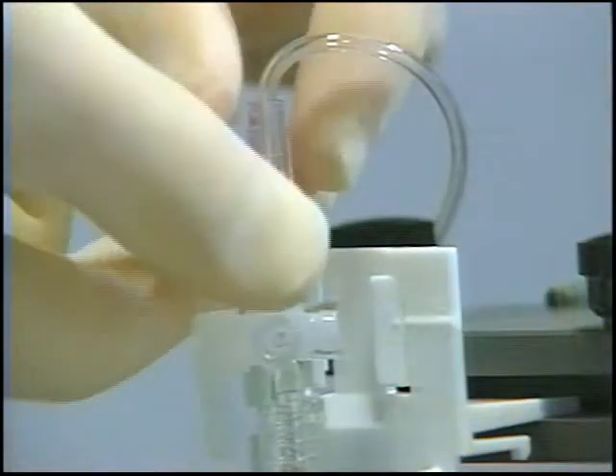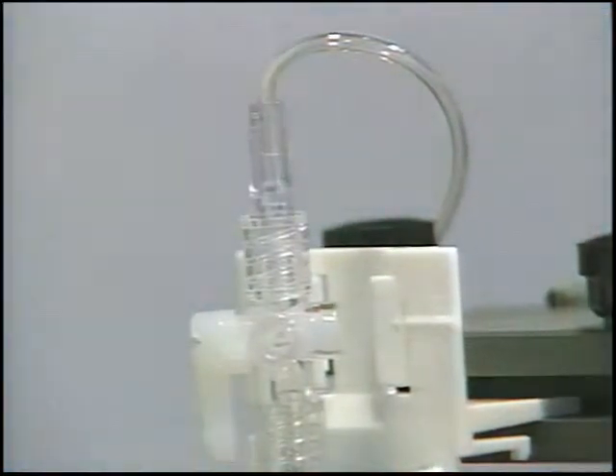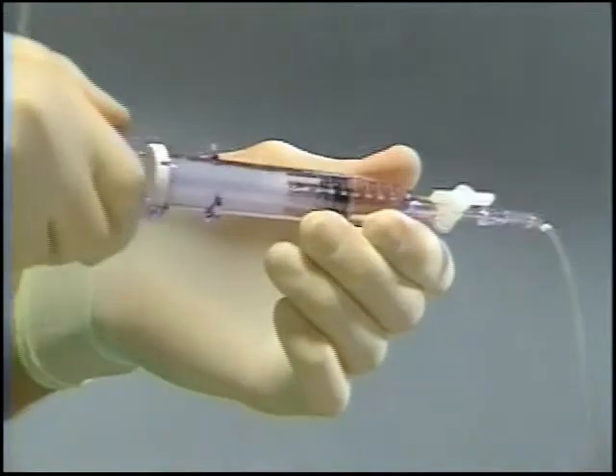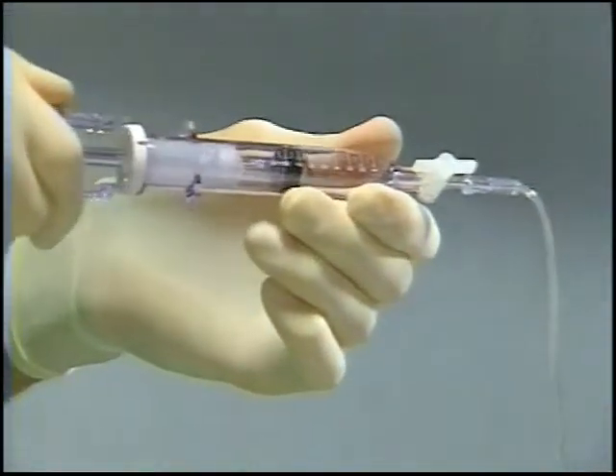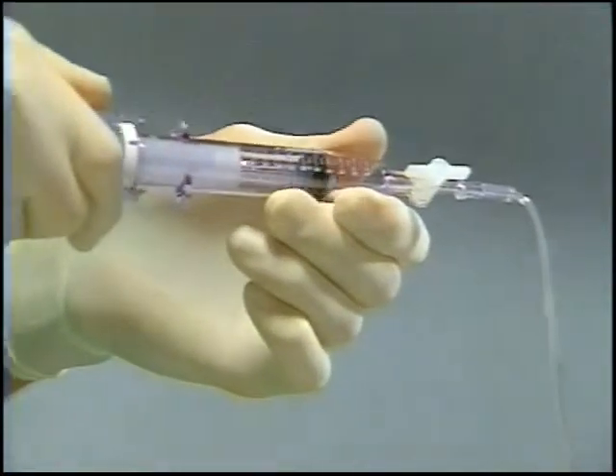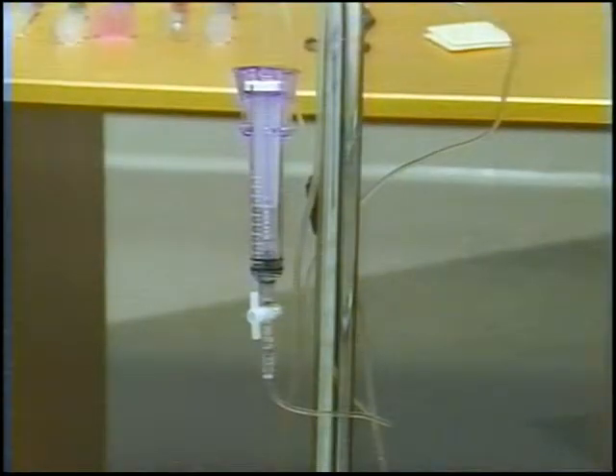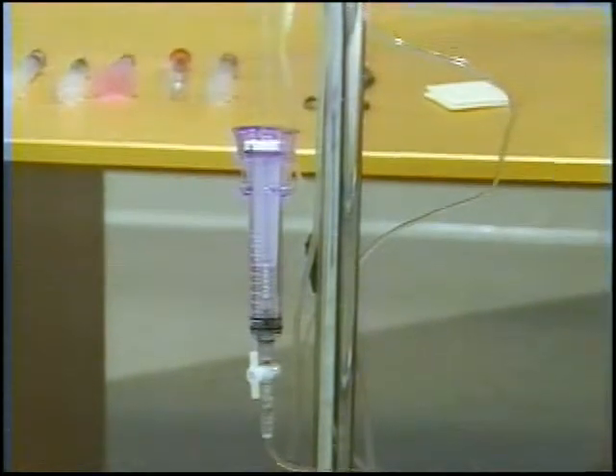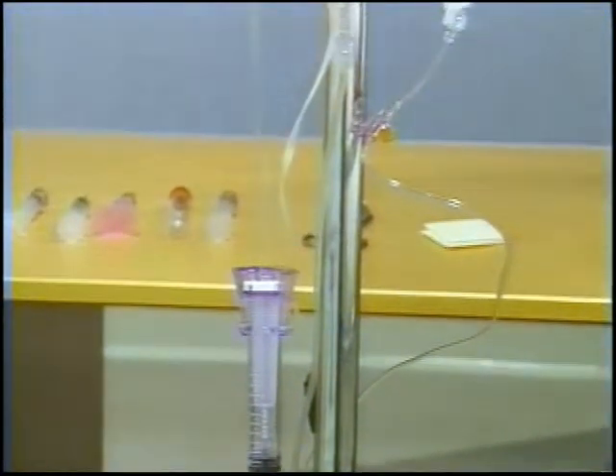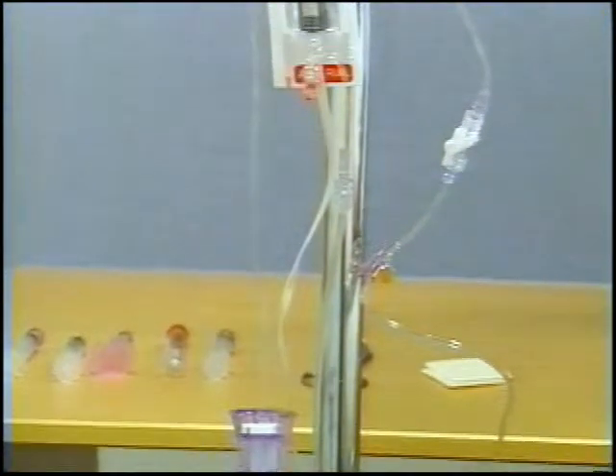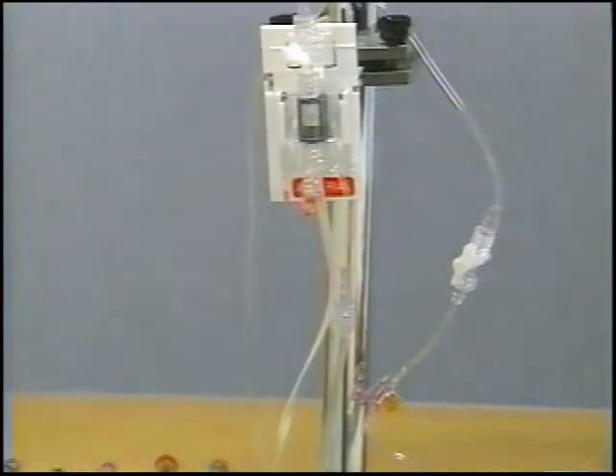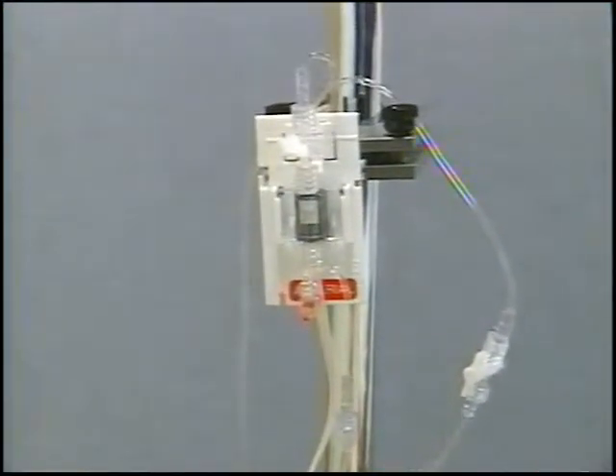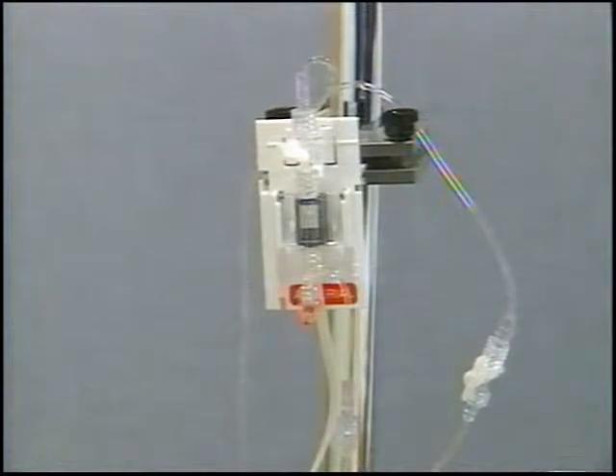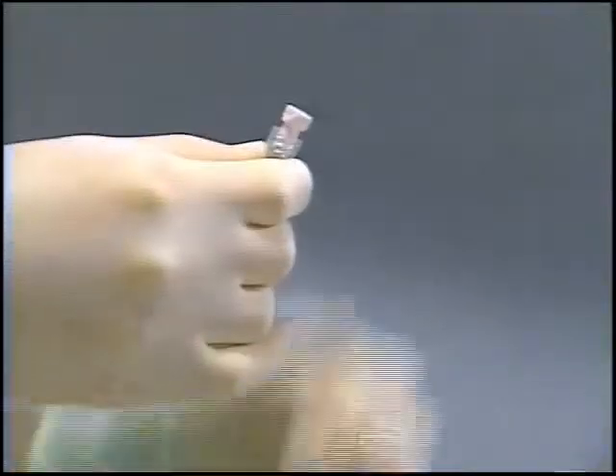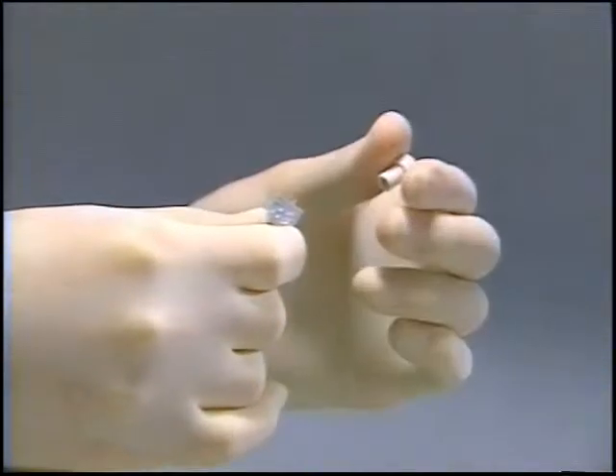First, ensure that all connections are secure. Before priming and setup, pull back on the Safeset plunger once or twice to ensure smooth operation. Set up and prime the administration set and transducer according to the normal operating procedure as detailed in the product instructions. Once the administration set and transducer have been properly primed, remove the white cover at the patient connector to prepare to flush the patient line.